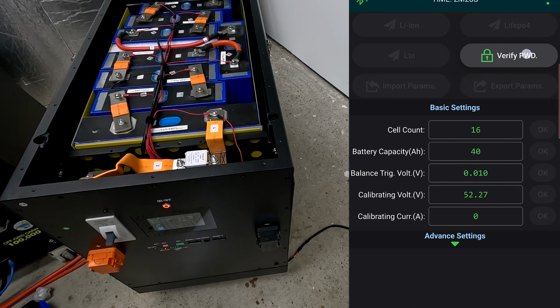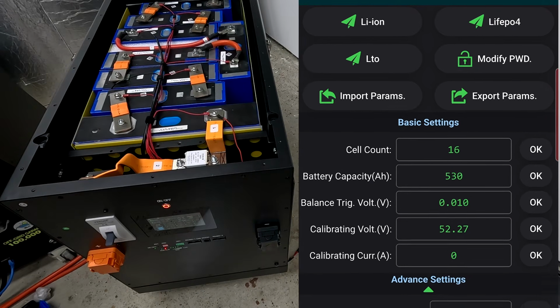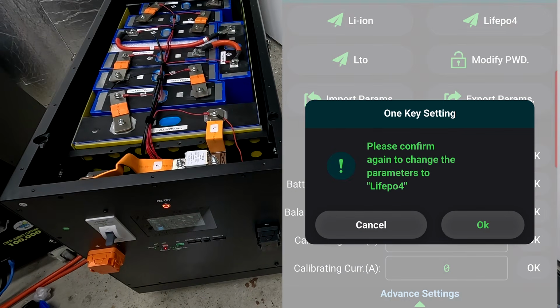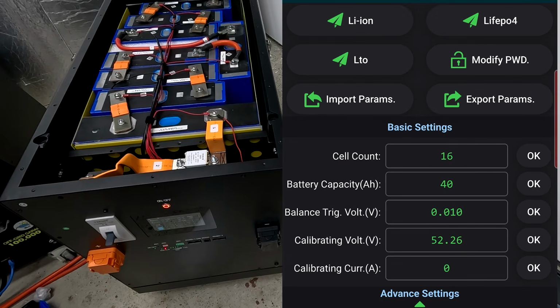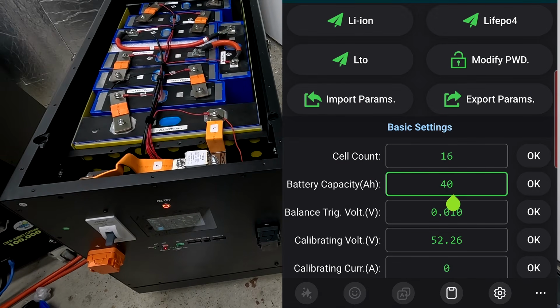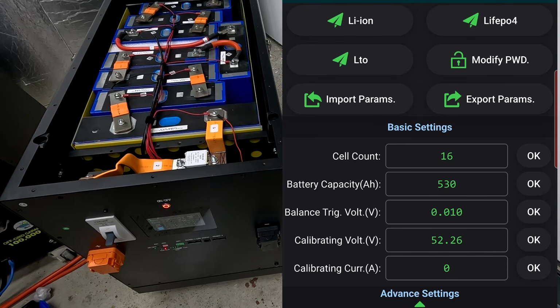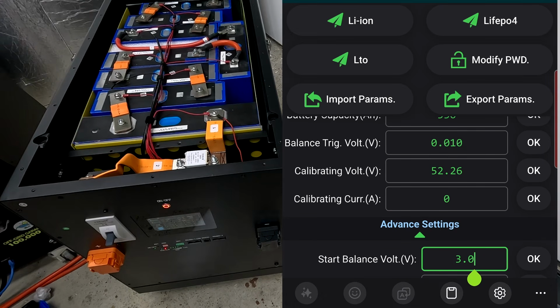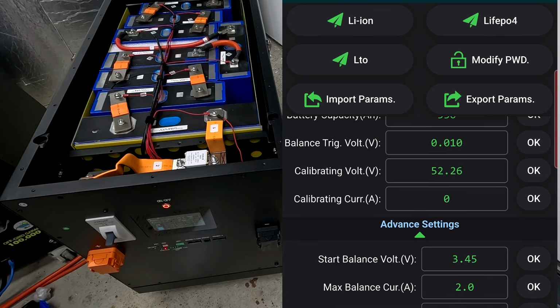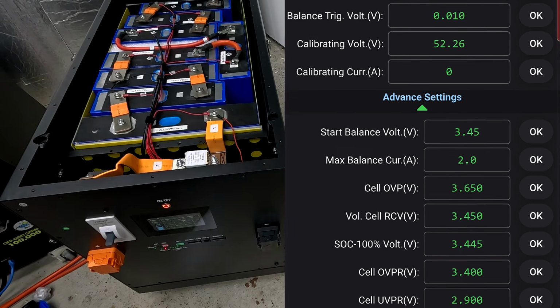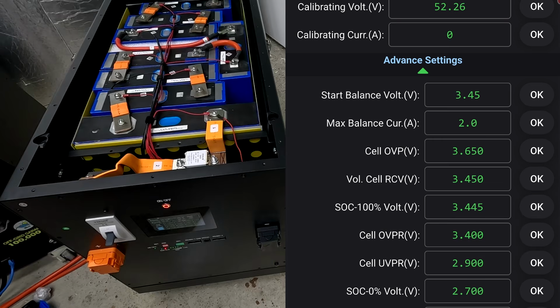So going to settings, first thing we want to do is click on lithium iron phosphate up here and get the settings right for that. Then set the battery capacity to 530 ampere hours. 10 millivolt deviation, calibration, that's all right. Balancing start voltage 3.45, cell overvoltage protection 3.65, 3.4, that's all good.